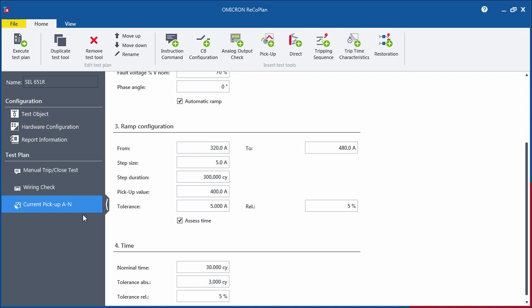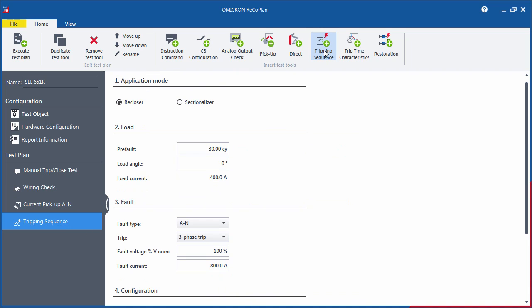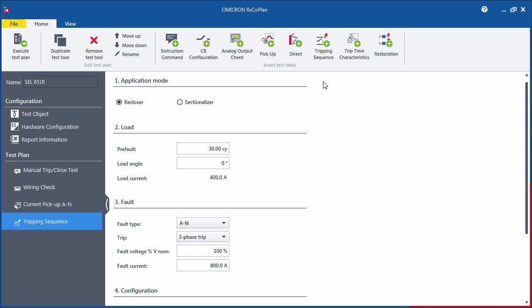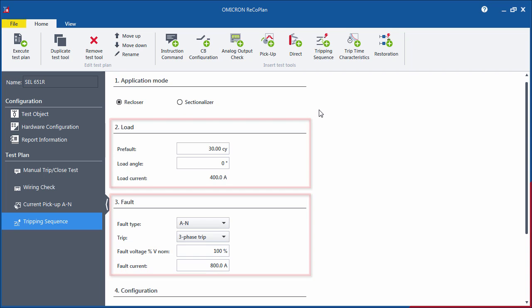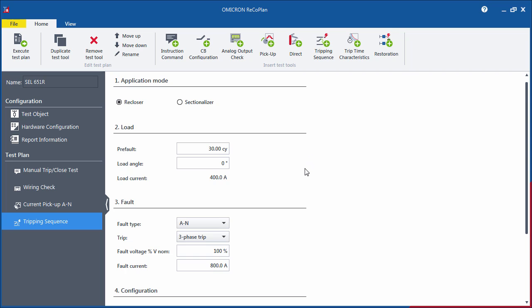With the Tripping Sequence Test tool, you can check the correct reclosing performance of recloser and sectionalizer controls. Let's imagine that you want to test the full sequence to lockout of the recloser control. The pre-fault and fault conditions are specified as a first step.